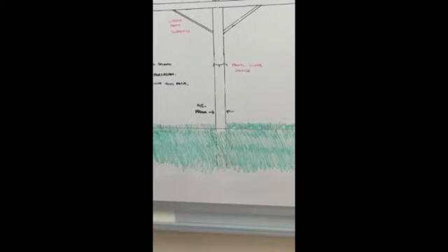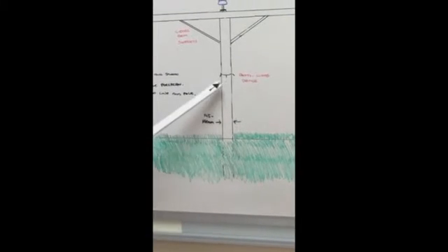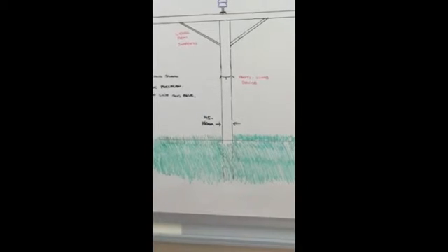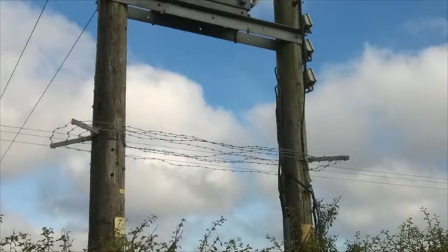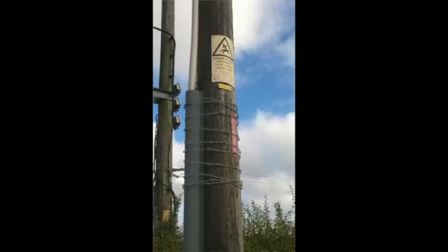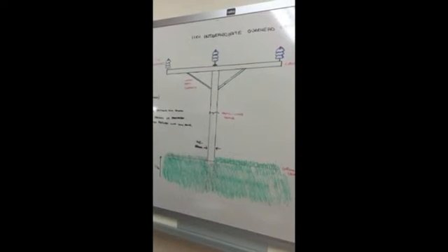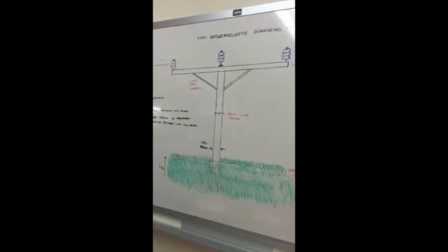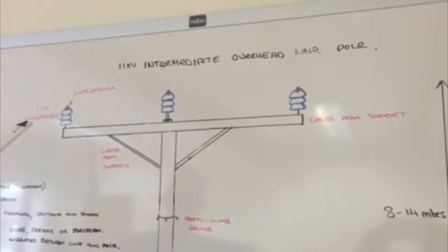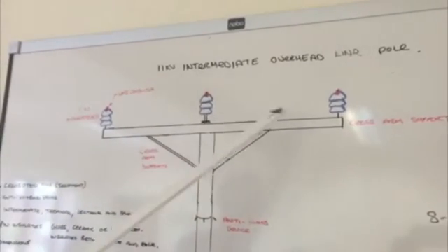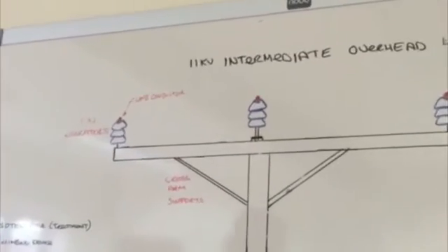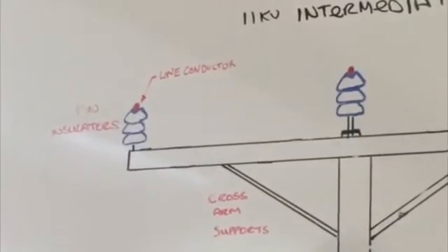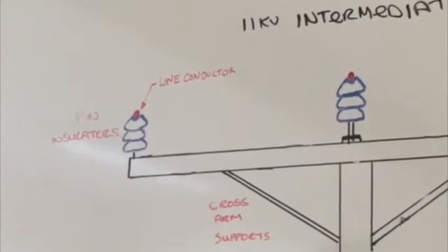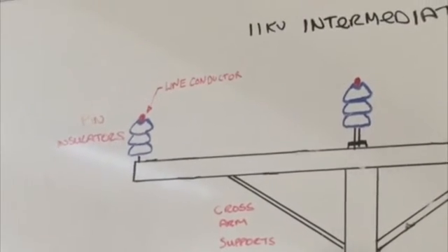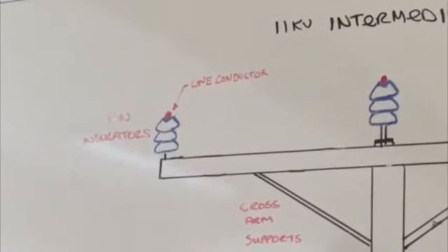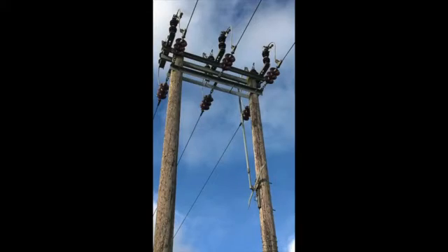Depending on the location of the pole, an anti-climbing device may be fitted. These come in a number of formats, whether it be a single metal piece or barbed wire. To extend the life of the pole, it is treated with creosote. This is to prevent it from rotting. As you can see, there are 3 pin insulators at the top of the pole. These insulators insulate the line conductor from the pole. They're shaped in such a way that the rain runs off them, keeping the underside dry and non-conductive. They can be made out of glass, ceramic or porcelain.